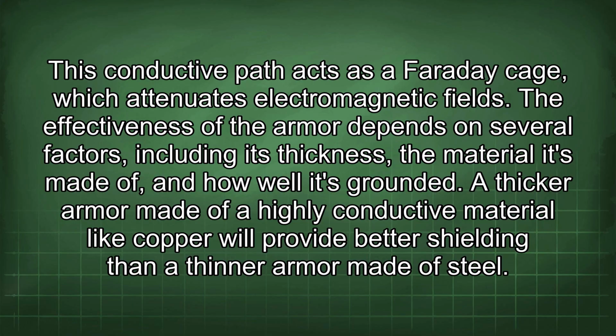The effectiveness of the armor depends on several factors, including its thickness, the material it's made of, and how well it's grounded. A thicker armor made of a highly conductive material like copper will provide better shielding than a thinner armor made of steel.